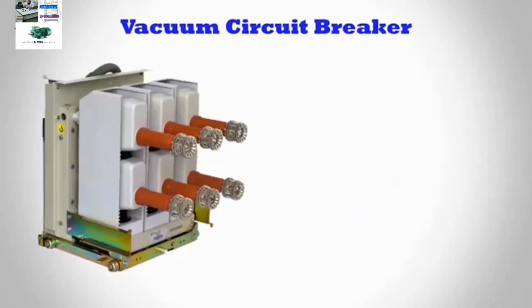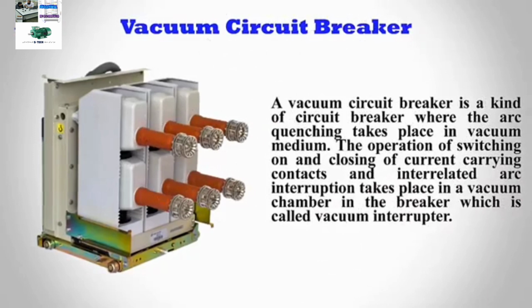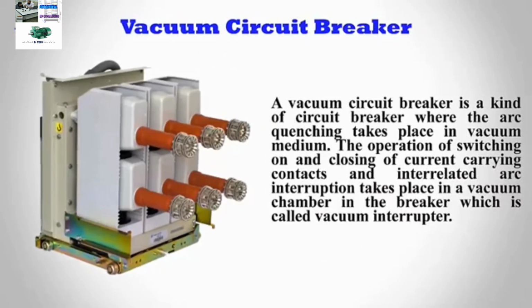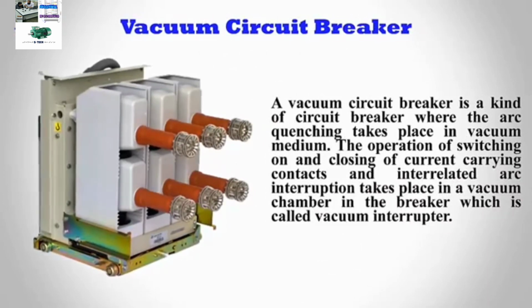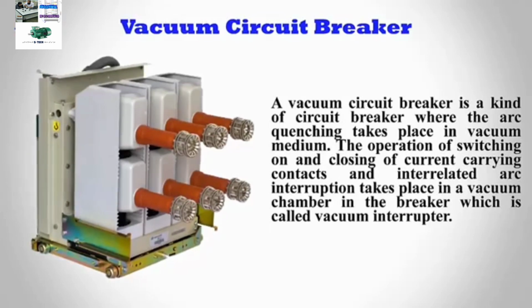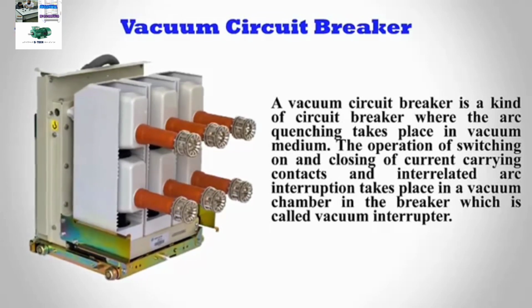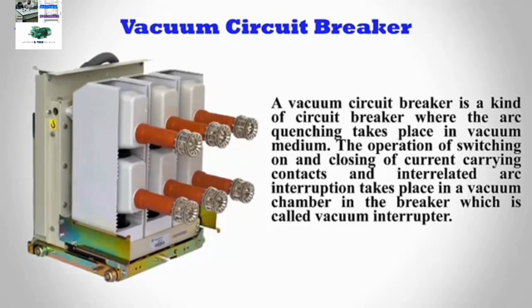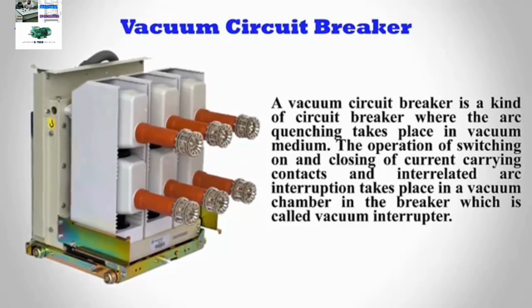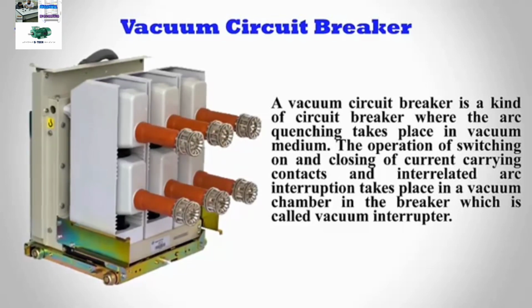A vacuum circuit breaker is a kind of circuit breaker where the arc quenching takes place in a vacuum medium. The operation of switching on and closing the current carrying contacts and the interrelated arc interruption takes place in a vacuum chamber in the breaker, which is called a vacuum interrupter.